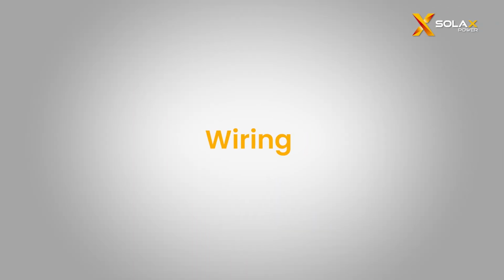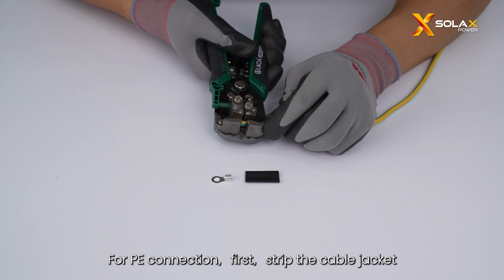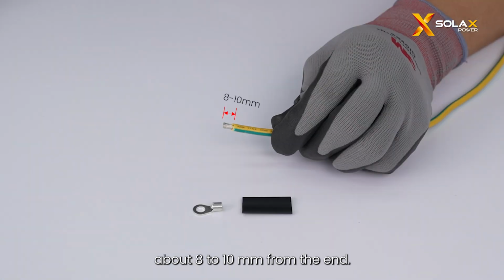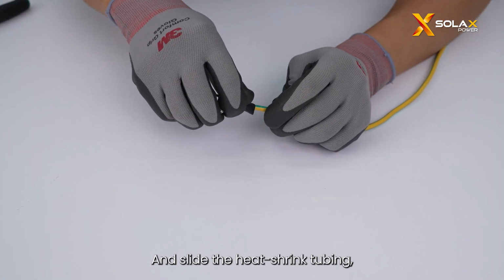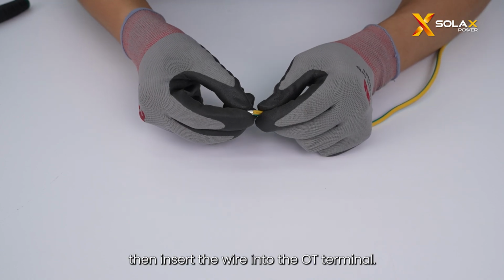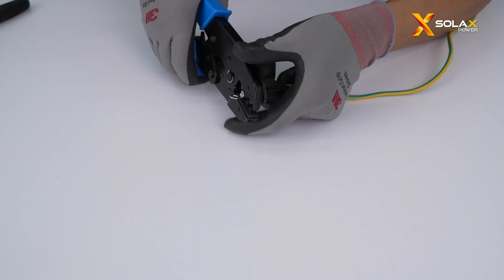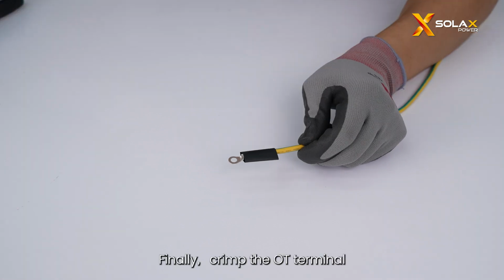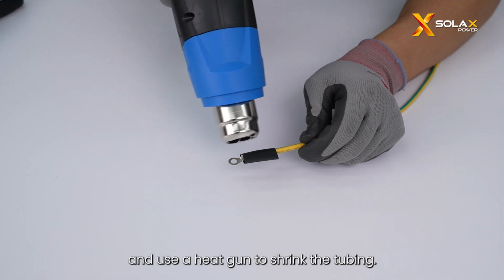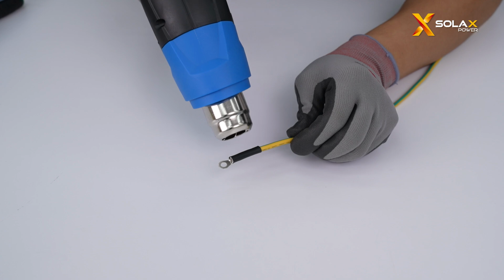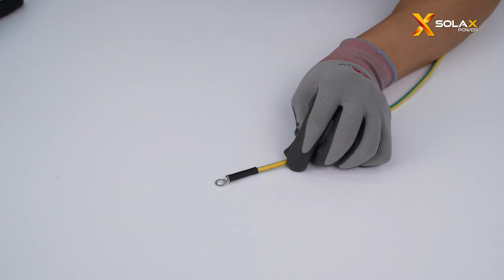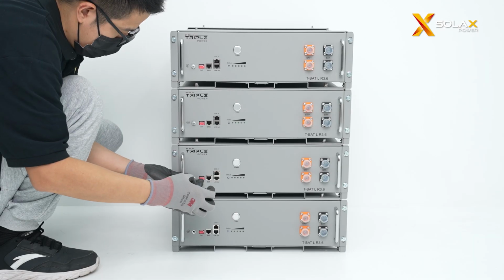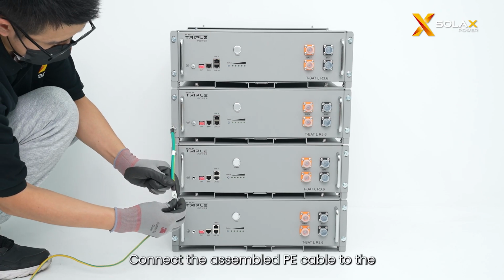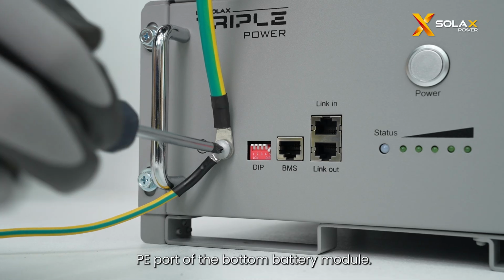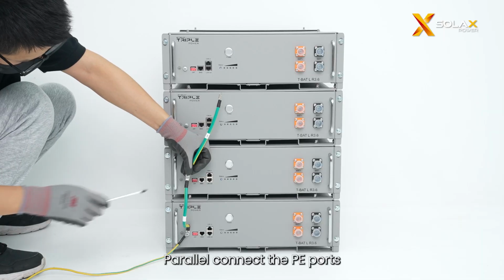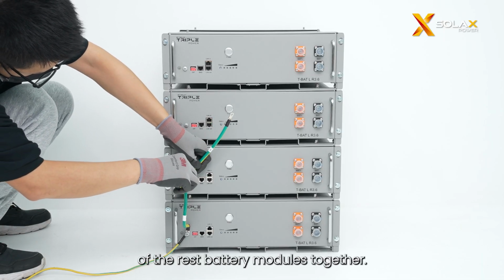Next, we'll move on to the wiring session. For PE connection, first strip the cable jacket about 8 to 10 mm from the end, and slide the heat shrink tubing, then insert the wire into the OT terminal. Finally, crimp the OT terminal and use a heat gun to shrink the tubing. Connect the assembled PE cable to the PE port of the bottom battery module. Parallel connect the PE ports of the rest of the battery modules together.